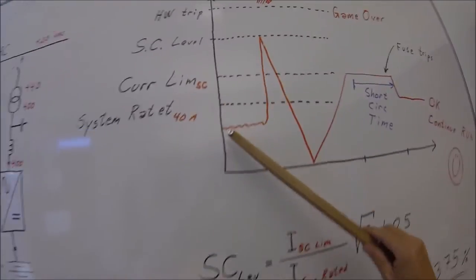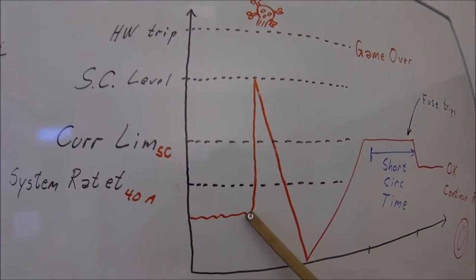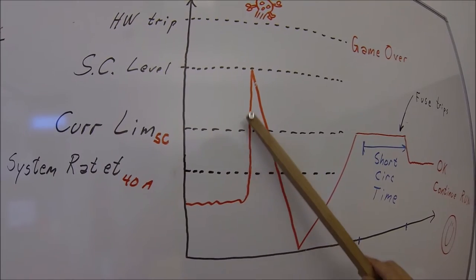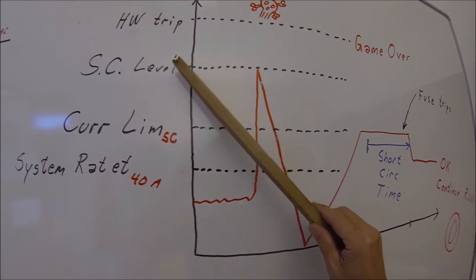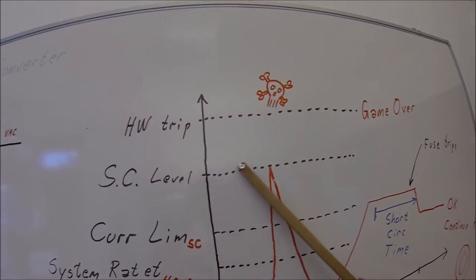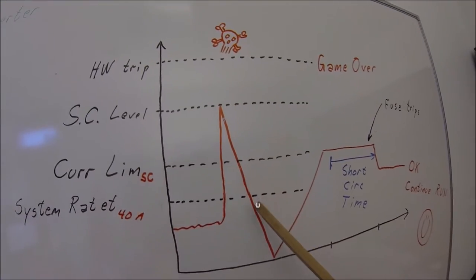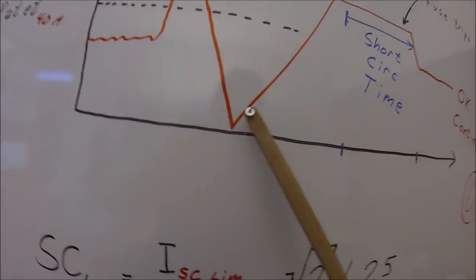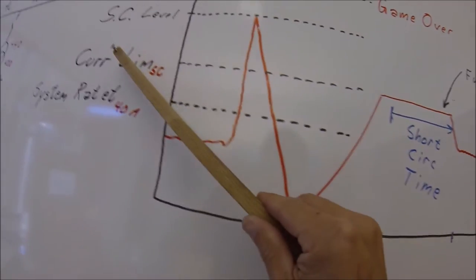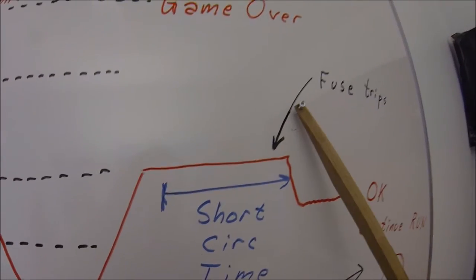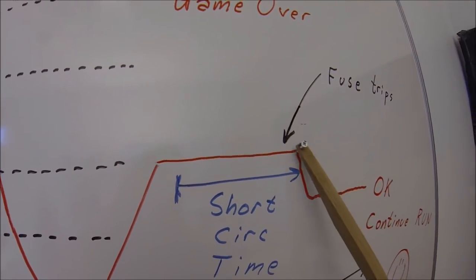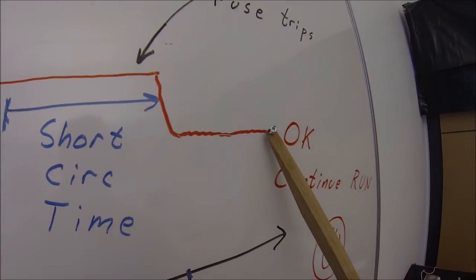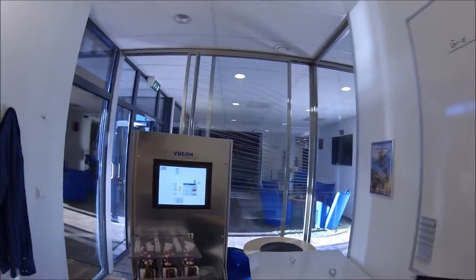We are running a consumer. There is a short circuit and the short circuit is detected by the drive which limits the current here. It cuts off the current, goes down to zero, then a current controller takes the current up to this level, blows the fuse, then re-establishes the grid and all the other consumers should be good.